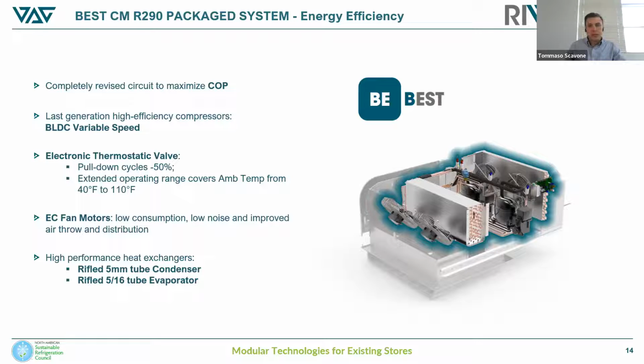The electronic thermostatic valve is fitted as standard on all models, allows the evaporator to be powered correctly in all operating conditions, and combined with the pressure probe and the new management of the evaporator fans, it reduces the pull down cycle by about 50%, so ensuring significant energy saving during this phase.